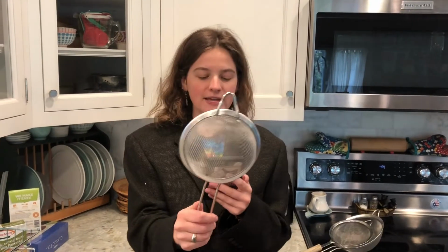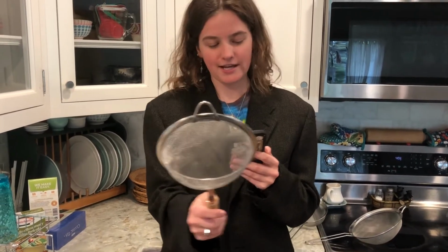This filters the water to collect and separate smaller particles. There are 3 different kinds of filter media: single, dual, and multimedia. Single media filters collect usually only sand and sometimes crushed anthracite coal. Dual media filters collect sand and anthracite. Multimedia filters collect sand, anthracite, and garnet. The design parameters for the filtration system are loading rates, flow rates, total surface area, surface area of each filter, and number of filters.